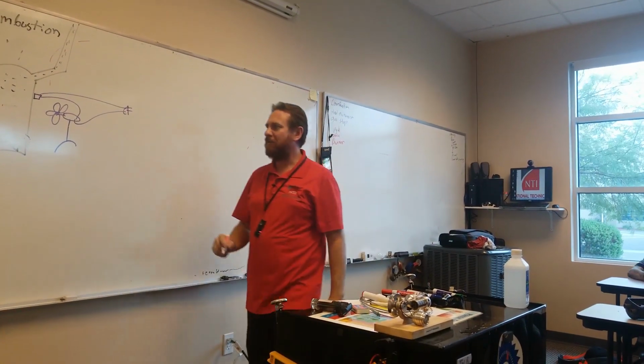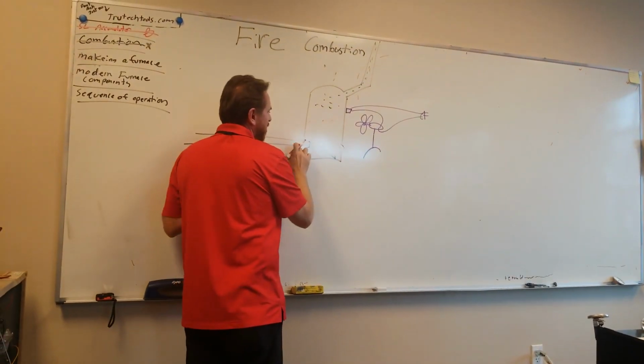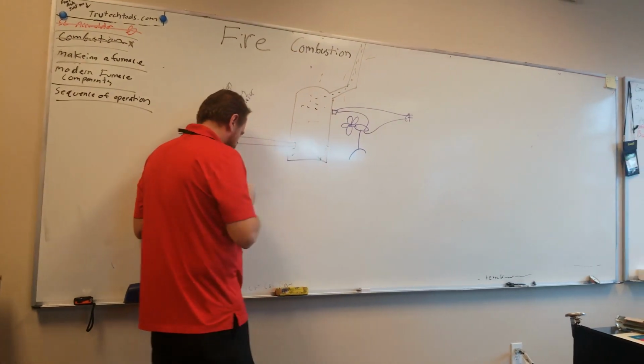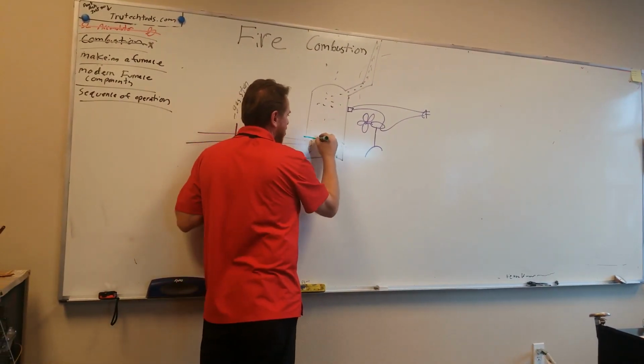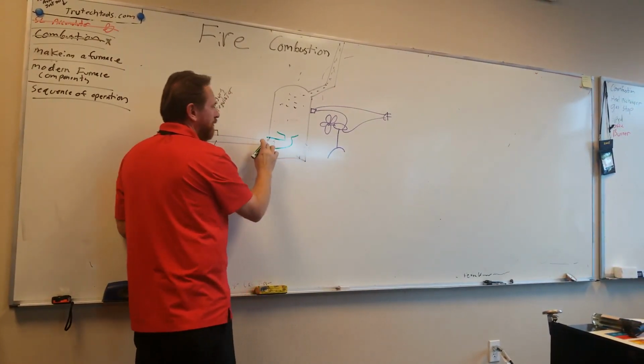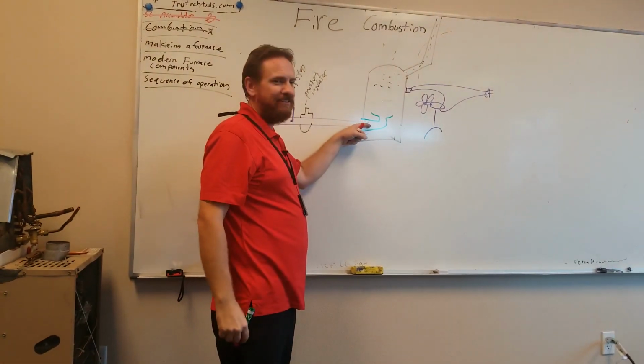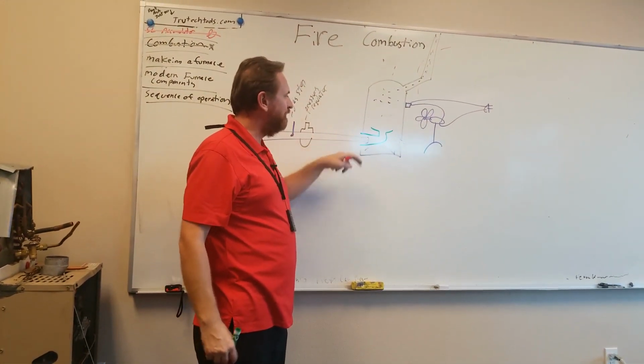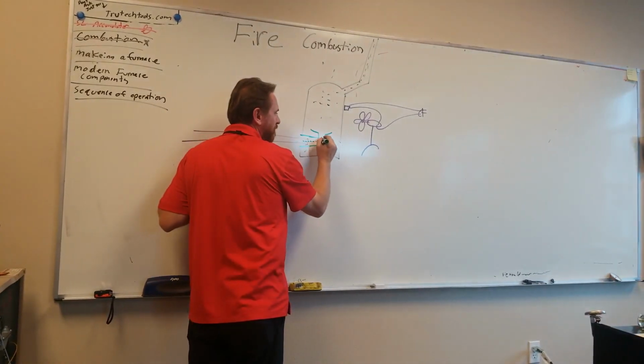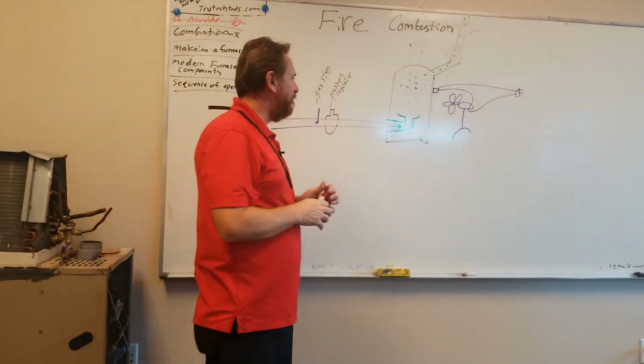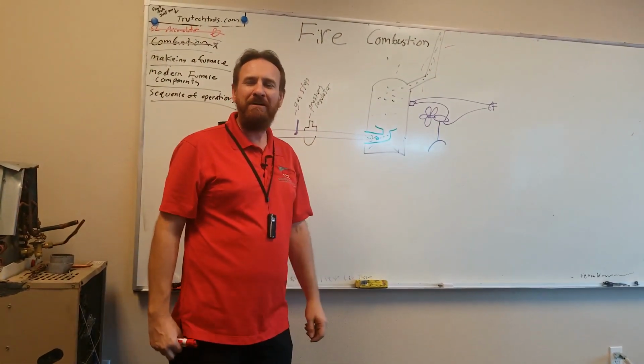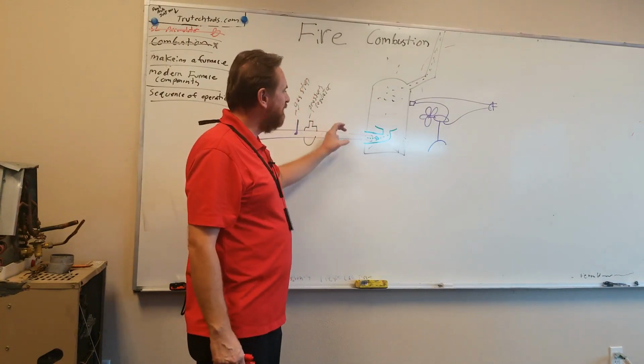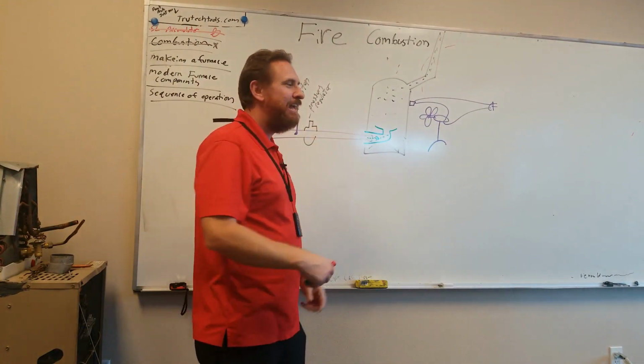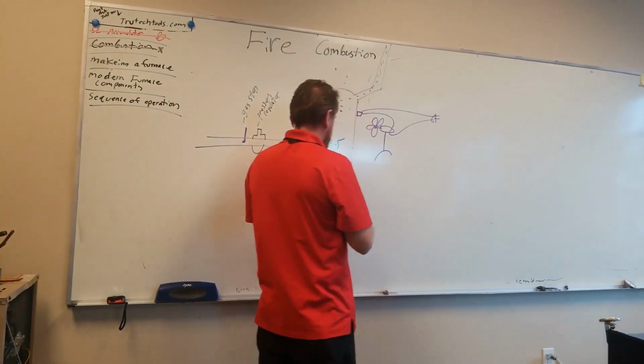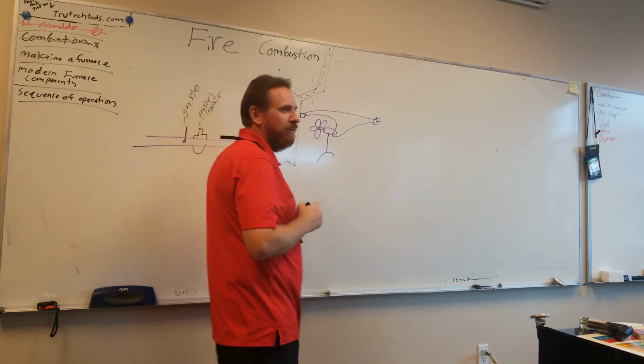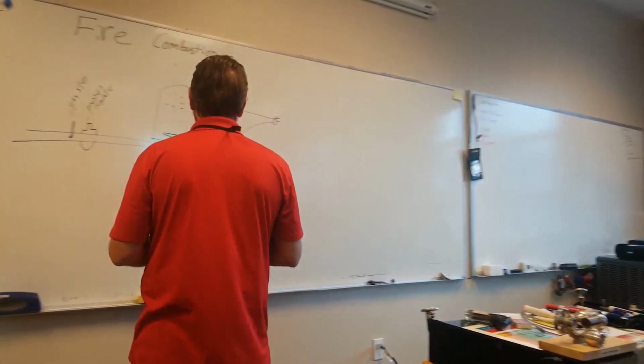What a burner is going to do is, one, mix the air and the fuel together. So we're going to bring a burner through here and allow it to mix the air and the fuel. Notice how I'm shooting the gas in. I also have gaps in the side. If I shoot gas in through the middle, it's going to create a bit of a vortex. And that vortex is going to be pulling air in from the side. What do I have to have for combustion? Oxygen. So it's pushing the gas and pulling oxygen beside it. The oxygen and the gas mix in the middle. And then the burner does two things. It mixes the fuel and the oxygen, and it also directs the flame.